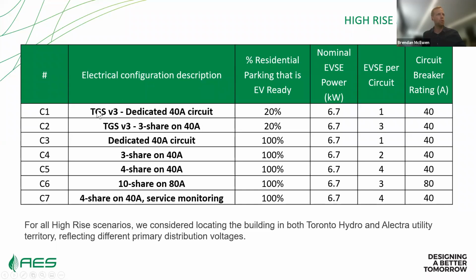The first 2 scenarios were meeting the Toronto Green Standard version 3 requirements that 20% of parking be EV ready. We looked at scenarios both with dedicated 40 amp circuits - one 40 amp circuit to each EV ready parking space - as well as a 3 share on 40 amp, which is allowed under TGS version 3. Then the remaining 5 scenarios, C3 through 7, are all 100% EV ready scenarios. The first is dedicated 40 amp circuits, then a 3 share on 40 amp meeting the current TGS performance requirements, then 4 share on 40 amp and 10 share on 80 amp, both meeting the performance requirements we analyzed, as well as a 4 share on 40 amp with service monitoring - also meeting those performance requirements and having that service monitoring to avoid any kind of transformer upgrade and utility service upgrade that can be costly for developers.